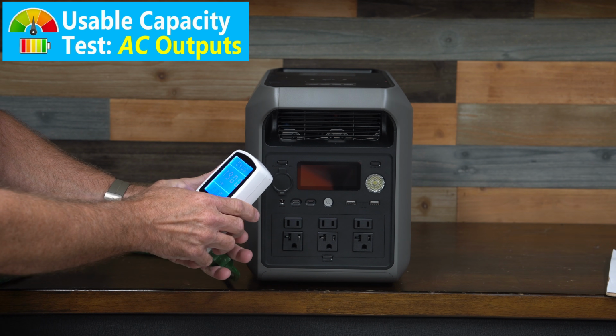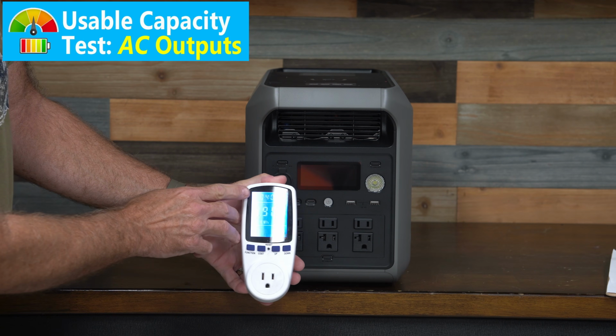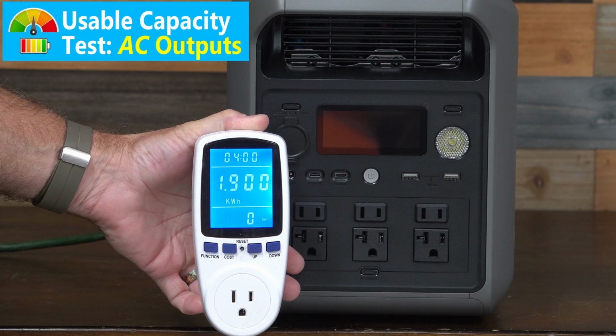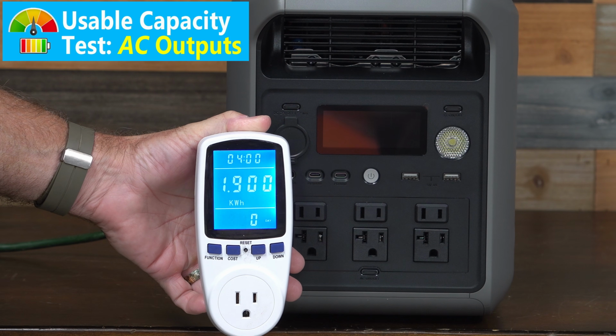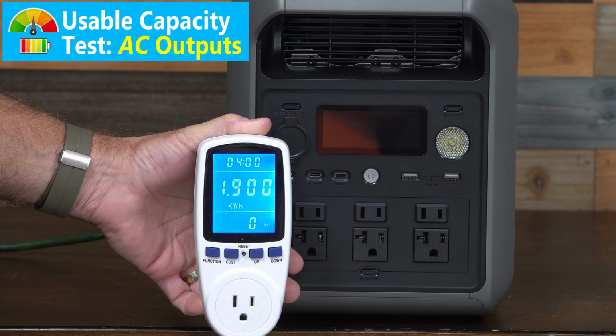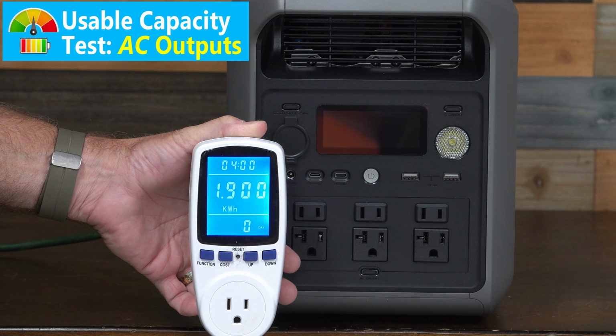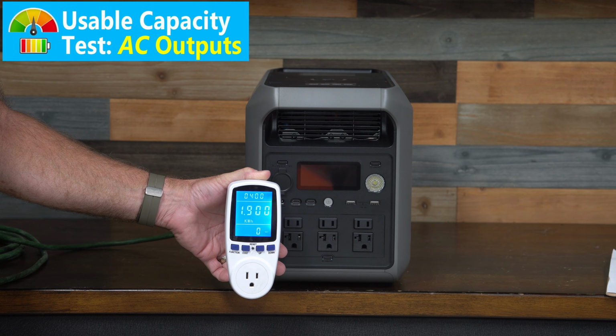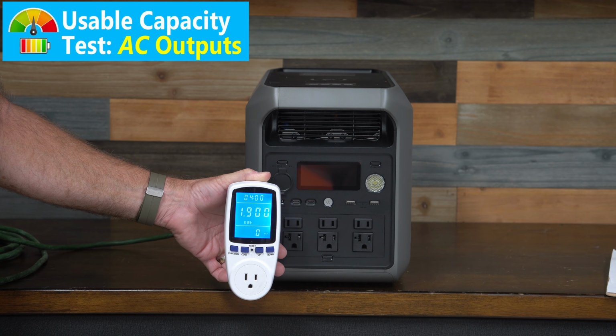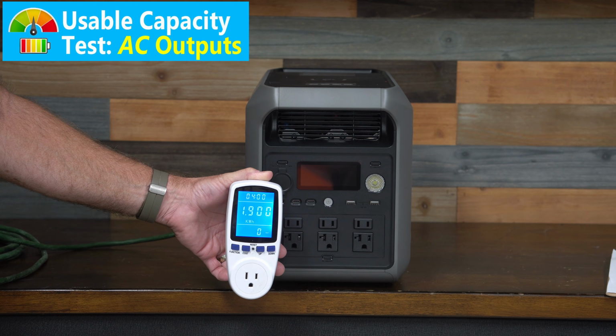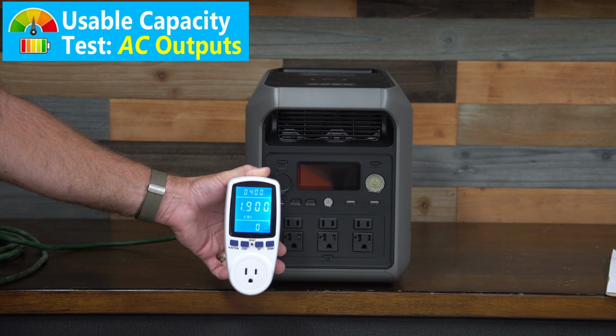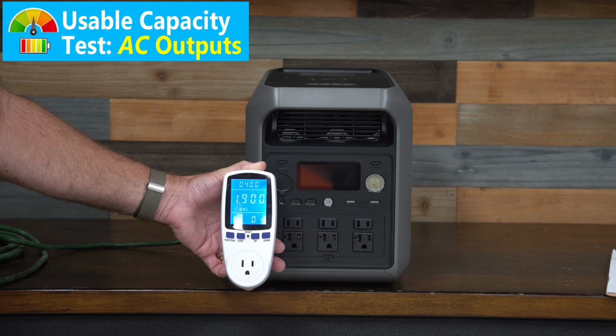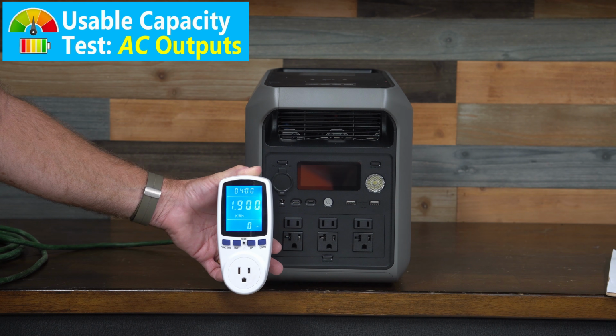So the test ran for 4 hours exactly, and we got a very good number. So 1,900 watt hours, or 1.9 kilowatt hours, out of that rated 2048, which is a well above average 92.7% of rated capacity. So very good usable capacity numbers through this AC inverter.